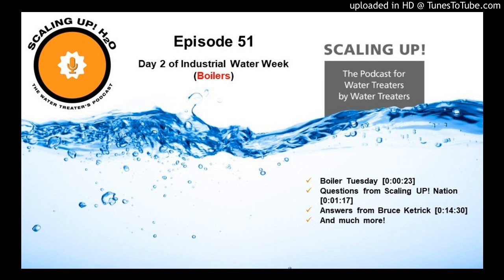Foaming can be caused by a number of issues. The most common reason that foaming is caused is because the solids in the boiler are too high. So perhaps we're running the concentration ratio too high in the boiler, or maybe there's an overfeed of something that's causing a lot of solids in the boiler.